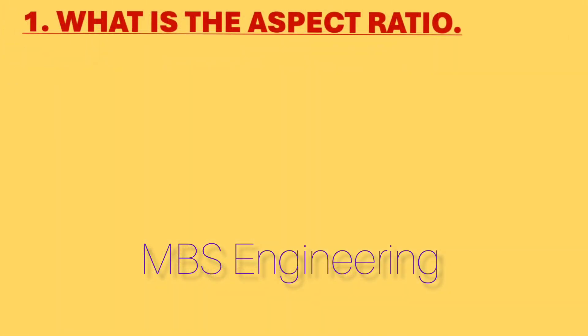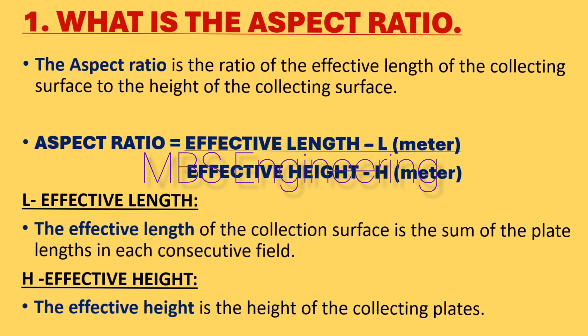The particulate is then attracted to the grounded collector plate and forms a dust layer on the plate. Next, we are going to understand what the aspect ratio is in the ESP. The aspect ratio is the ratio of the effective length of the collecting surface to the height of the collecting surface. The aspect ratio equals effective length in meters divided by effective height in meters.